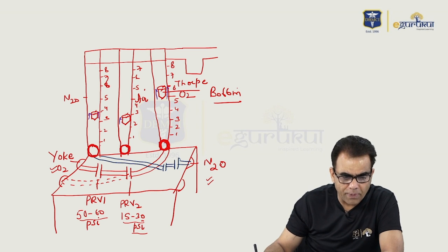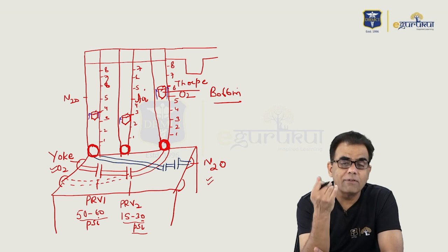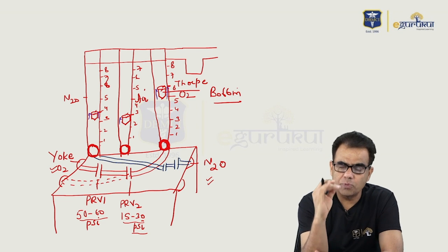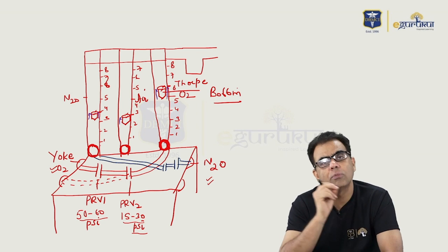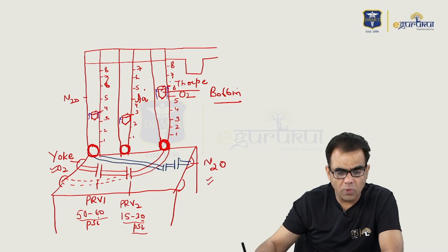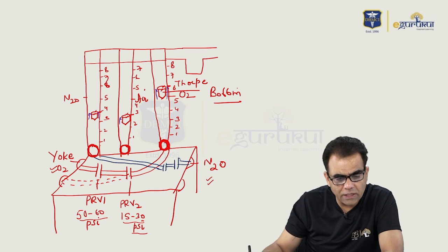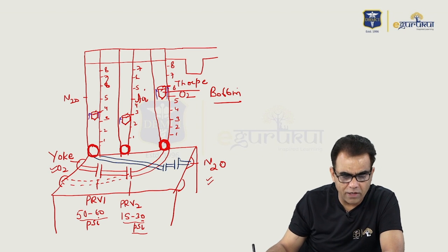It is the upper level of the bobbin which determines the flow rate — not the middle level or lower level. This has been asked two or three times in exams: which part of the bobbin determines the flow rate? It is the upper level. So if the flow rate of oxygen is six liters, you read the upper level of the bobbin. Flow rate of air is three liters — upper level. Nitrous oxide is four liters — upper level of the bobbin.